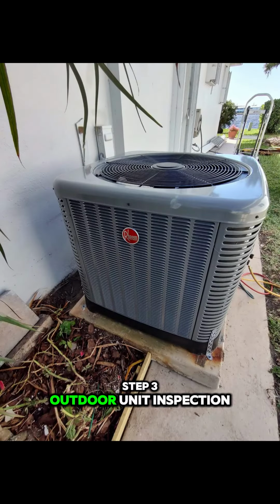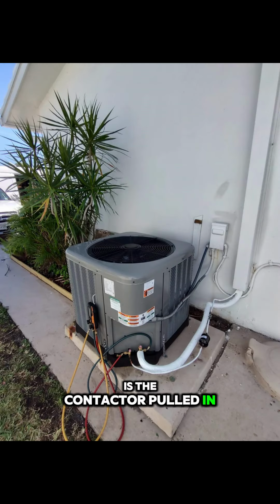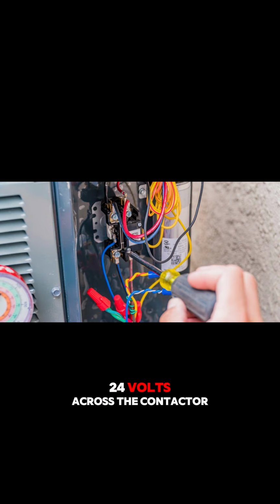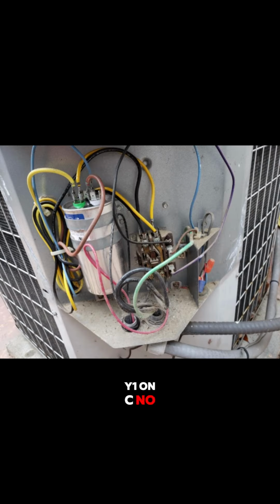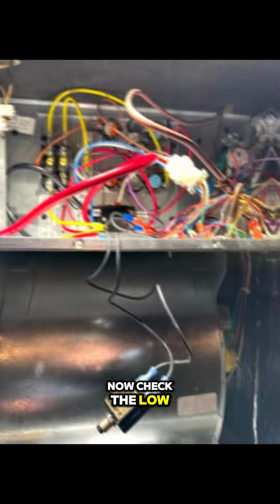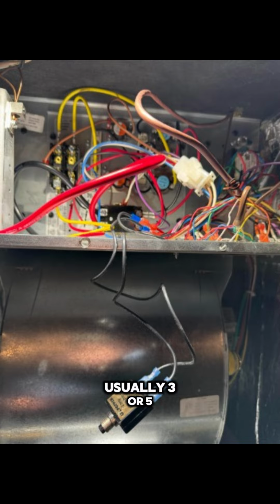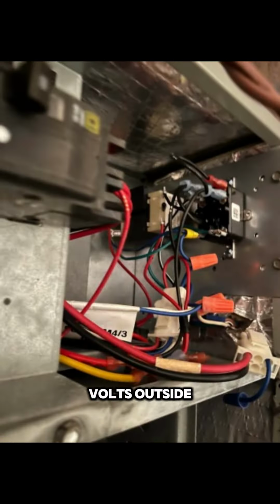Step 3. Outdoor unit inspection. Go to the condenser. Is the contactor pulled in? If not, test for 24 volts across the contactor coil, one lead on Y, one on C. No 24 volts? Now check the low voltage fuse in the air handler, usually 3 or 5 amps. If the fuse is blown, the system won't send 24 volts outside. Also check for float switch issues or faulty thermostat wiring.